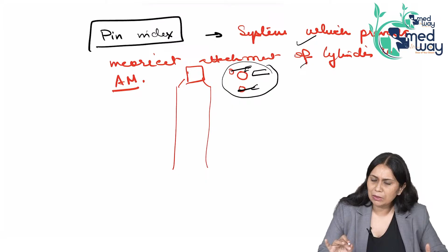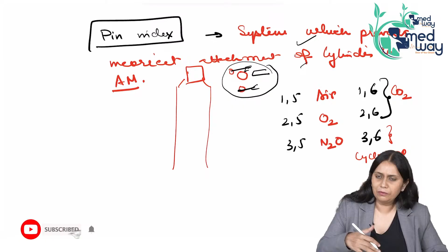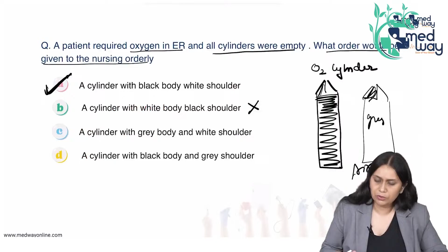So, remember the pin index follows the 15, 25, 35 and 16, 26 and 36 system. Now, 6 is like C. Gases starting with C come under the 16, 26, 36 system. 16, 26, carbon dioxide. 36, cyclopropane. Okay. 15, 25, 35: nitrous oxide, 3 atoms, 2 nitrogen, 1 oxygen, has 3, 5. Oxygen, 2 atoms, 2, 5, and air is a mixture, 1, 5. So, keep the pin index in your mind. Okay. So, this is all about the anesthesia machine questions which you need to cover.